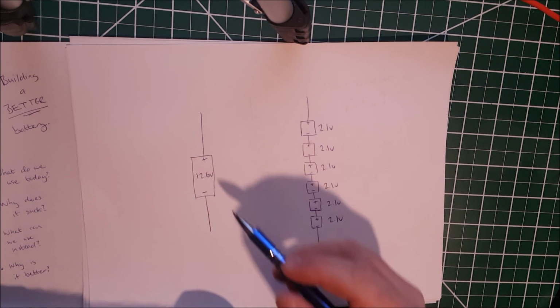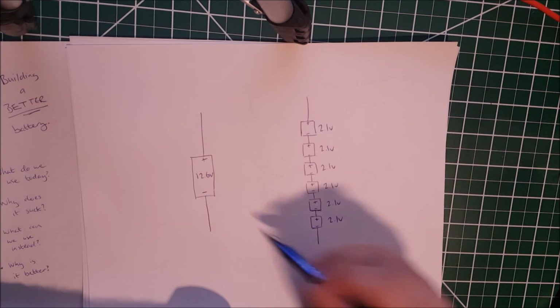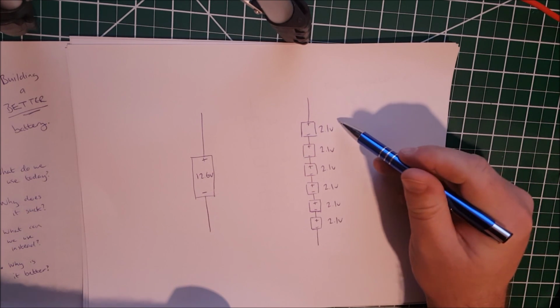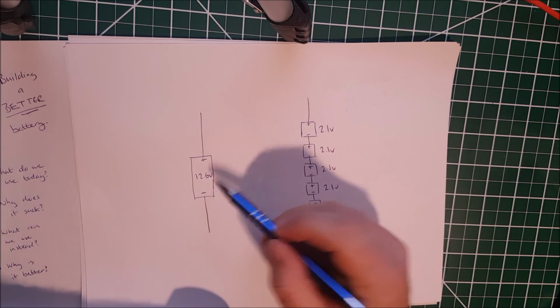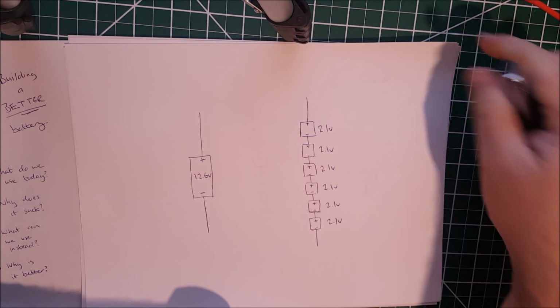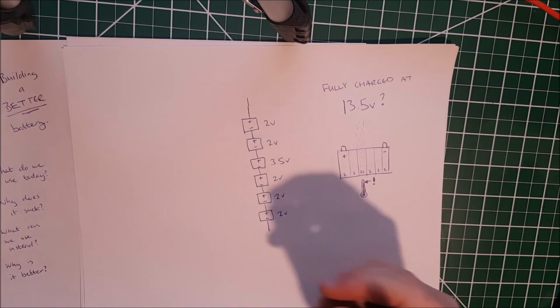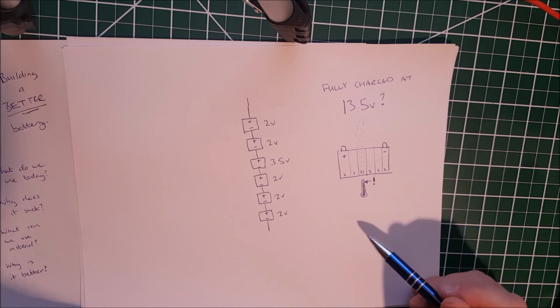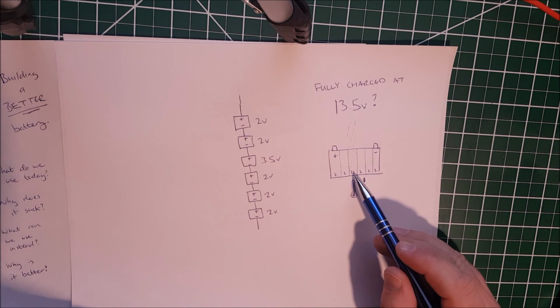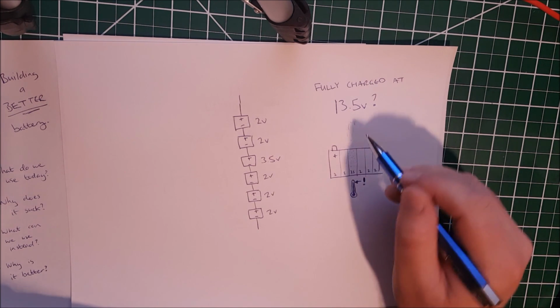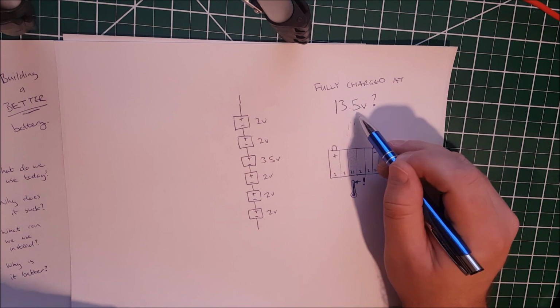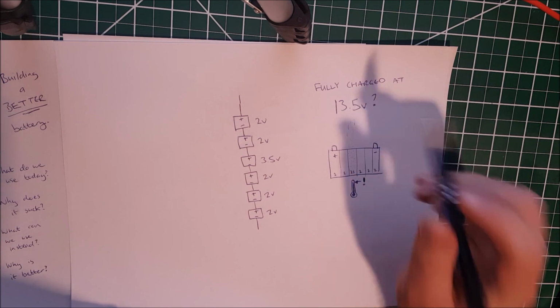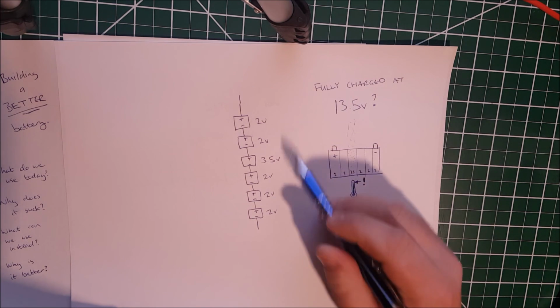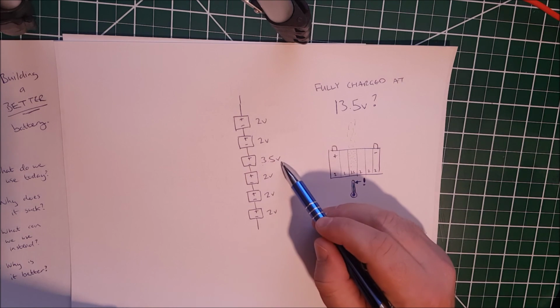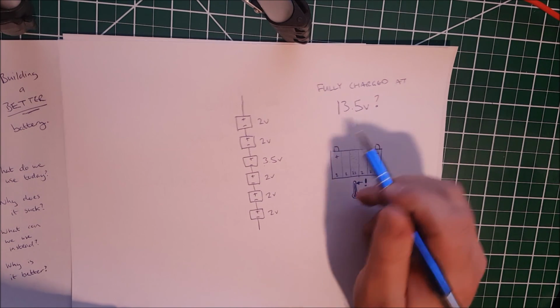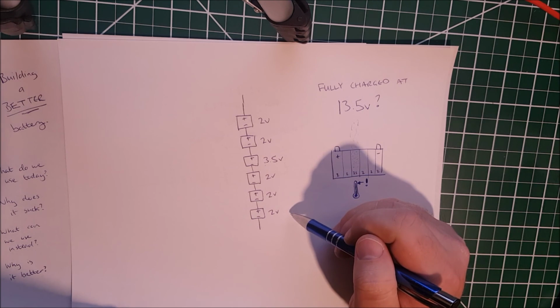So it's important to remember that a 12 volt lead acid battery in particular is made up from six cells. And if the battery was at 12.6 volts, then hopefully each cell would be at 2.1 volts. When a battery goes bad, it means that one of the cells has really gone out of whack. This is an example of a battery that you might think is fully charged because it's registering at 13.5 volts. However, five of the cells are at 2 volts, and one of them is at 3.5 volts. Now, ideally at 13.5 volts, every cell would be at 2.25 volts.